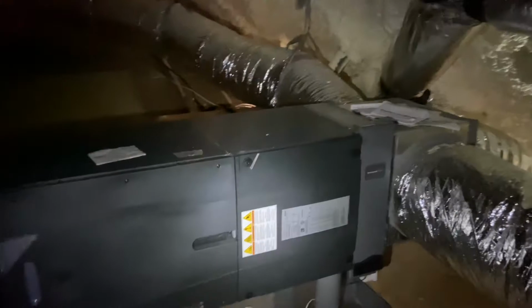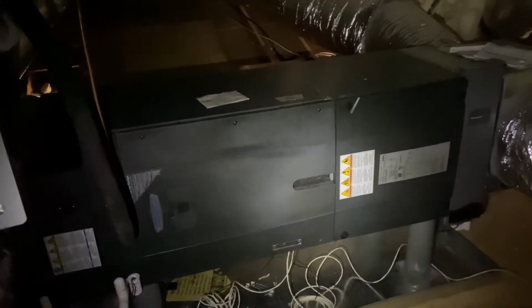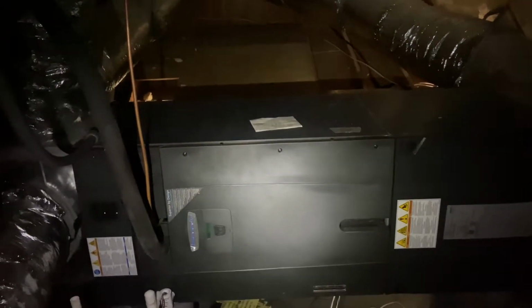And then we also have just another 20 amp circuit down to that outlet. That is for convenience, because you need to have a convenience outlet for the air handler per code for any technicians that come to work on it, as well as I need a 120 volt supply for the ERV system for ventilation for the system. So that's what you need for that.